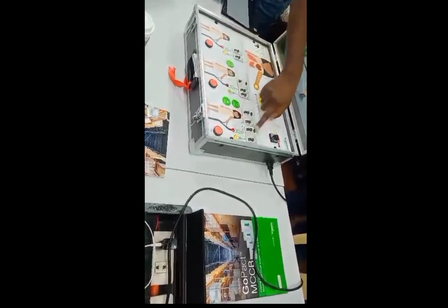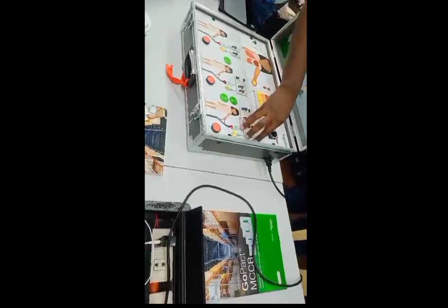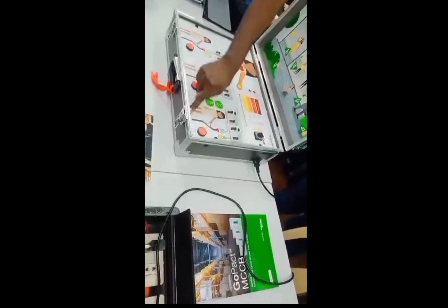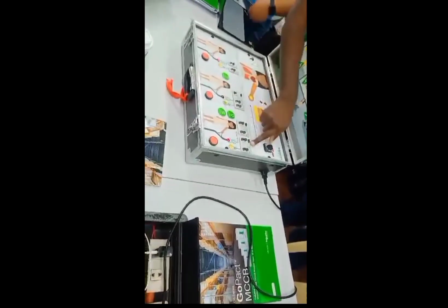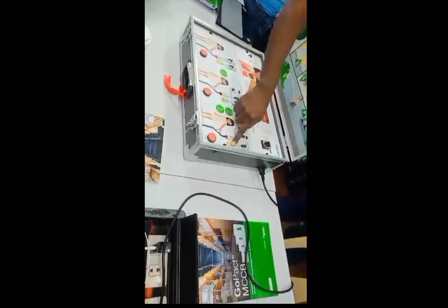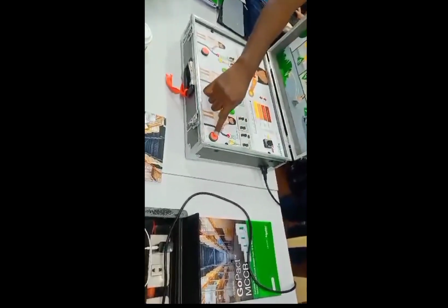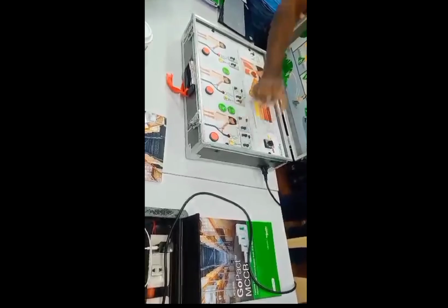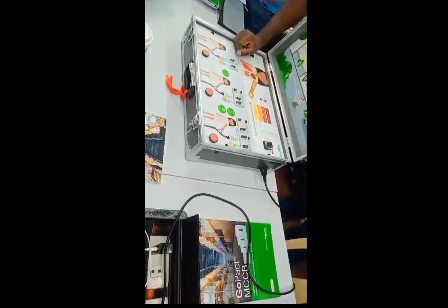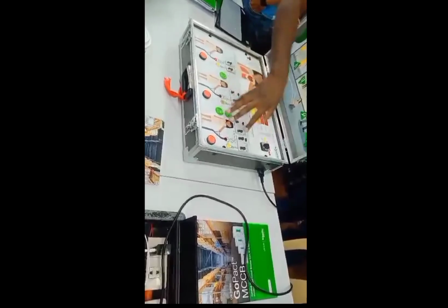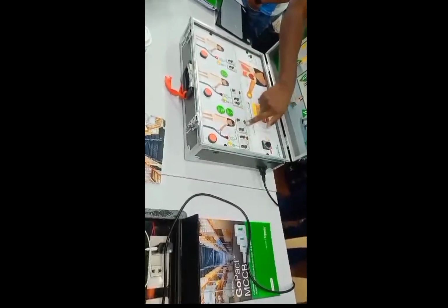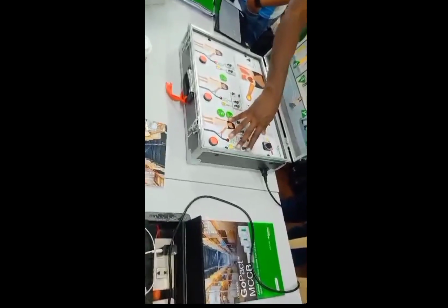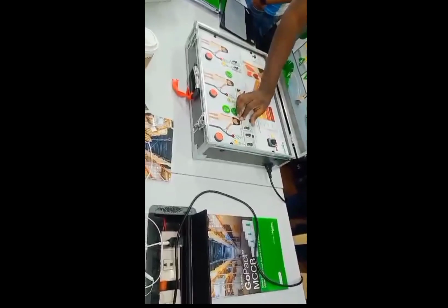And the third scenario is where you segregate the 2 circuits. So you have an RCD MCB pair for the socket outlets, RCD MCB pair for the lights. Now the fault will only happen on this line, and you only trip this side. So the lights continue to operate. So more expensive because you have 2 RCDs, but better continuity of service. You have only the portion that's affected going off.